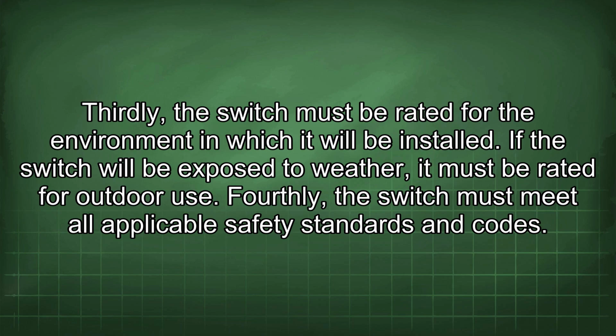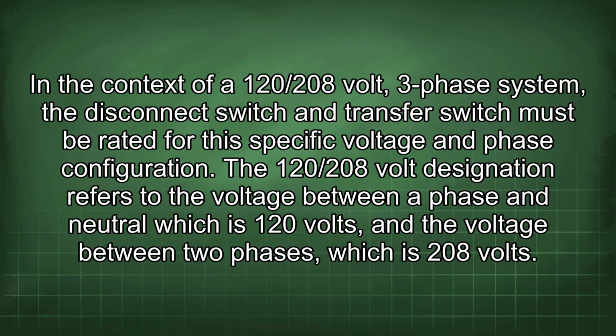Fourthly, the switch must meet all applicable safety standards and codes. In the context of a 120/208 volt three-phase system, the disconnect switch and transfer switch must be rated for this specific voltage and phase configuration. The 120/208 volt designation refers to the voltage between a phase and neutral, which is 120 volts, and the voltage between two phases, which is 208 volts.